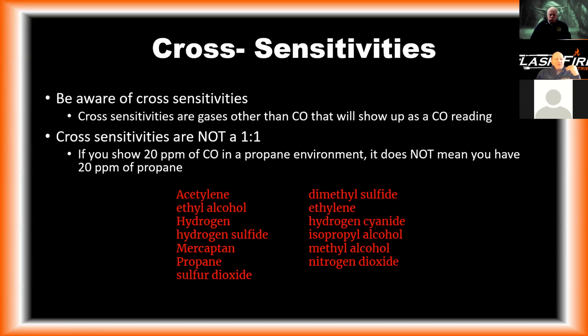But you have to be aware that if you go in for a CO alarm sounding and you're getting readings on your carbon monoxide meter, there is potentially another gas that's affecting it. If you can't figure out, hey, there's nothing burning here, there's no boiler, we shut it down, and we're still getting readings on our CO meter, what's going on here? Some of the most common cross sensitivities in the industry: acetylene. If you have a very light acetylene leak, a lot of the time it will register on the CO meter before it registers on the LEL sensor.